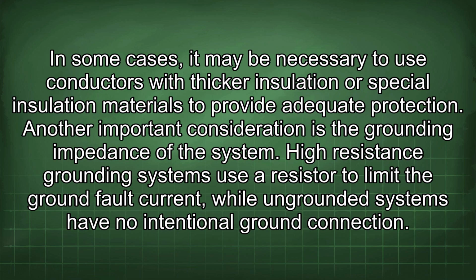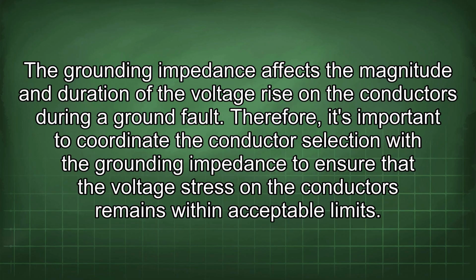High-resistance grounding systems use a resistor to limit the ground fault current, while ungrounded systems have no intentional ground connection. The grounding impedance affects the magnitude and duration of the voltage rise in the conductors during a ground fault. Therefore, it's important to coordinate the conductor selection with the grounding impedance to ensure that the voltage stress on the conductors remains within acceptable limits.